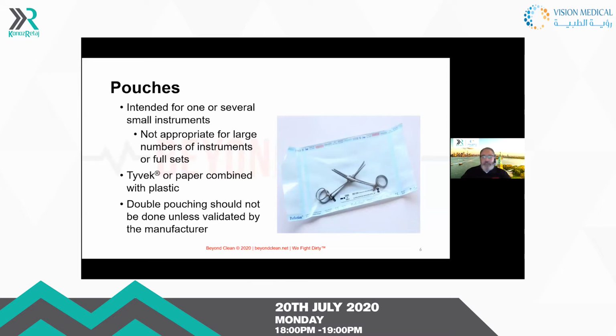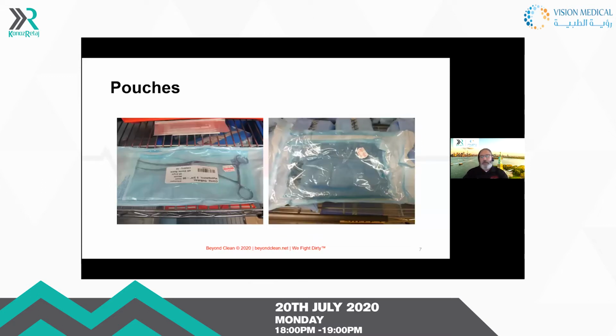I always like to add pictures of devices that I find in facilities when I perform sterilization audits. And as you can tell, on the left, they have nicely folded the inner peel pouch, which is an incorrect practice. This is something that you always want to look for, to make sure that the pouches sequentially fit inside the other pouch. When you fold them, it adds additional layers that the steam sterilant will need to penetrate, and it can impact the efficacy of your sterilization.